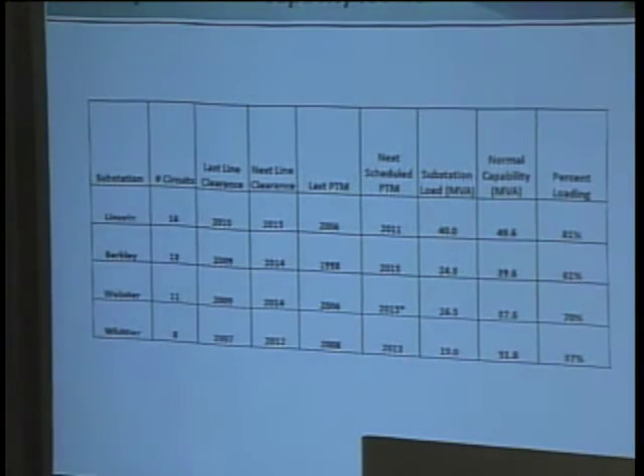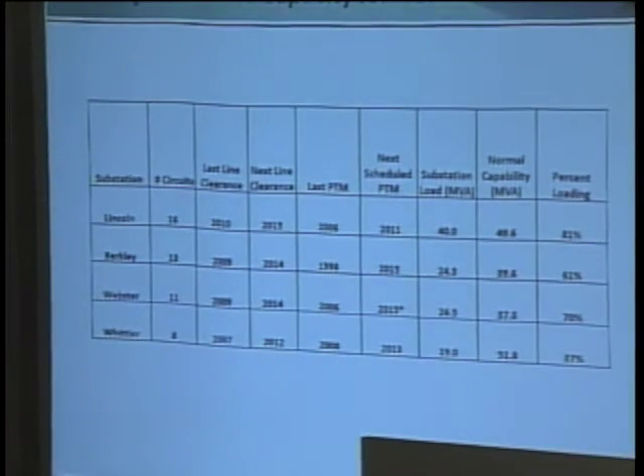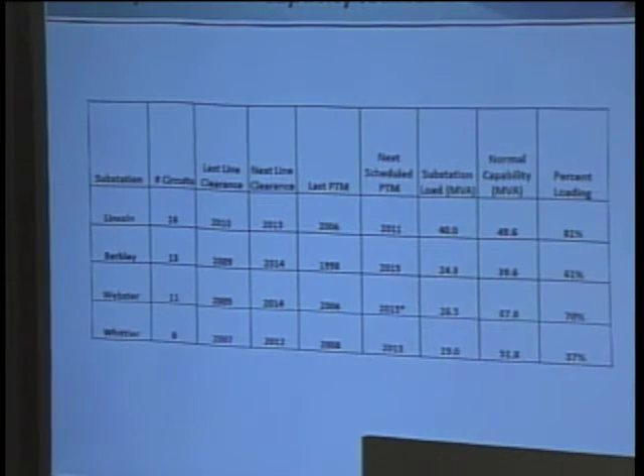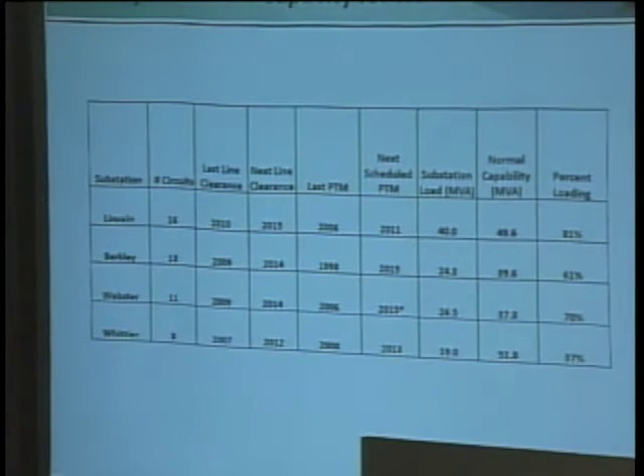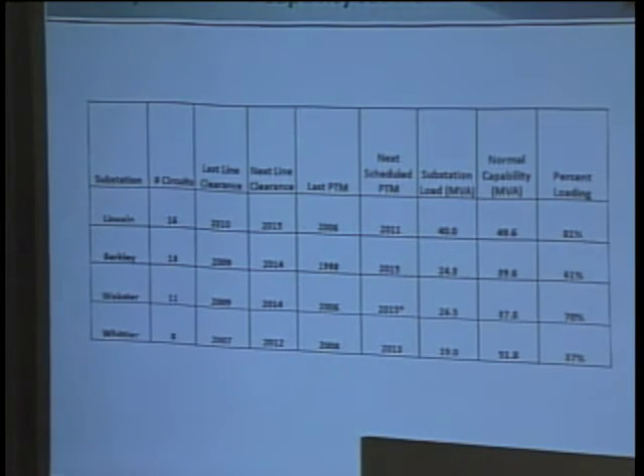Berkley, the available capacity for new growth. What this shows is primarily the number of circuits out of each substation, the line clearance, the pull tap maintenance, and the substation loadability. This is the capacity of each of the substations. Note that the load is third from the last, and the normal capability, which is its capacity, is second to the last. And then the percent loading is in the final column.